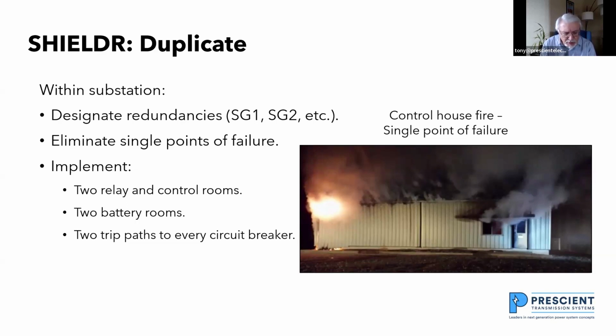This means we should be implementing 2 relay and control rooms, 2 battery rooms, and 2 trip paths to every circuit breaker. When I talk about trip paths, I mean you can't put the redundant cables in the same cable tray or the same conduit. This is something the nuclear power industry has been doing for the last 40 years, and it's something we should embrace.